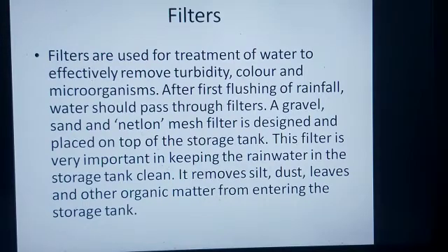Next is filters. Filters are used for the removal of turbidity, meaning any solid particles present, or any color, microorganisms, anything that needs to be removed. The filters remove these materials effectively. After first flushing of rainfall, water should pass through the filters. A gravel, sand, Netlon mesh filter is designed and placed on the top of the storage tank. This filter is very important in keeping the rainwater in the storage tank clean. It removes silt, dust, leaves and other organic matter from entering the storage tank.